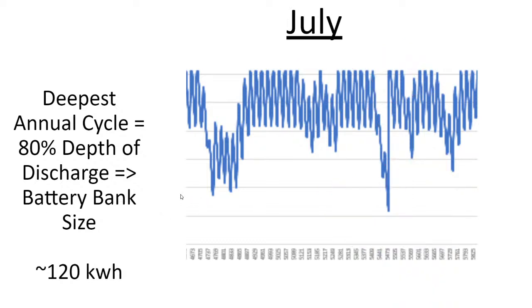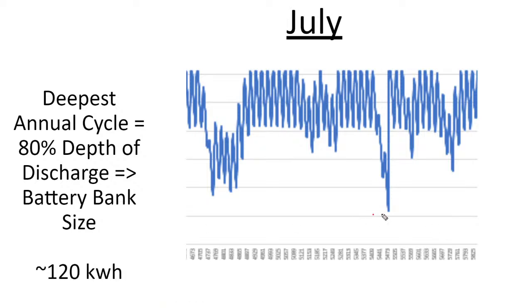You get settings that'll tell you, once the battery bank reaches this far of a depth of discharge, should you stop selling back to the grid. An intelligent grid sellback would not just tell you the minimum threshold. The Schneider inverter that lacks intelligence for selling back to the grid says, well, stop selling when the battery voltage reaches this level, but it only gives you one rate of discharge. And that's problematic because the home load actually jumps up and down.